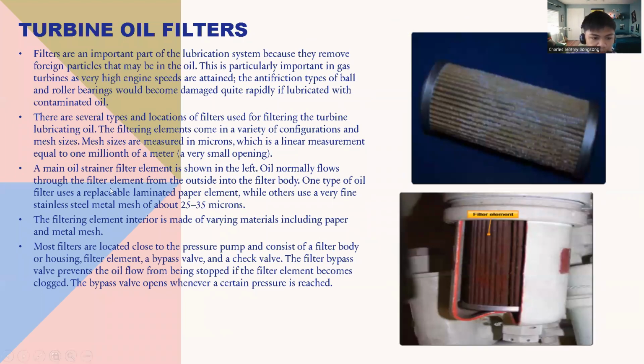Next is turbine oil filters. Filters are an important part of the lubrication systems because they remove foreign particles that may be in the oil. This is particularly important in gas turbines as very high engine speeds are attained. The anti-friction types of ball and roller bearings would become damaged quite rapidly if lubricated with contaminated oil. So we use these filters so that we will not have any damage on the roller bearings and ball bearings.